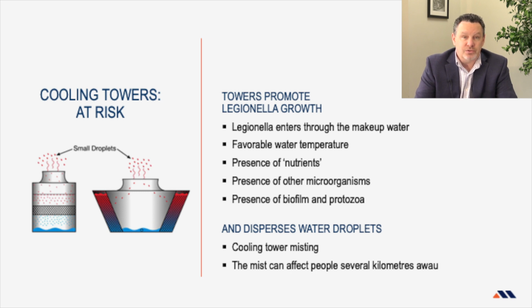Obviously, if your cooling tower is using lake or river water that's just filtered, in that case you'll have higher concentrations to deal with. But it's mostly from the makeup water. There are some very rare occasions where you can get cross-contamination from other cooling towers, like your neighbors or other buildings or plants within striking distance that are not being treated properly. But it's not the most common source.